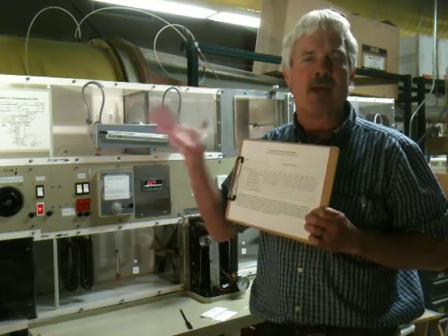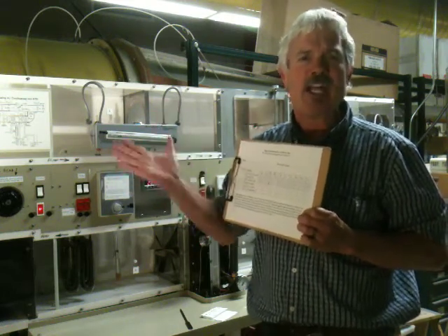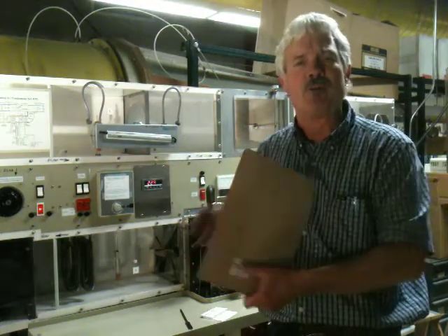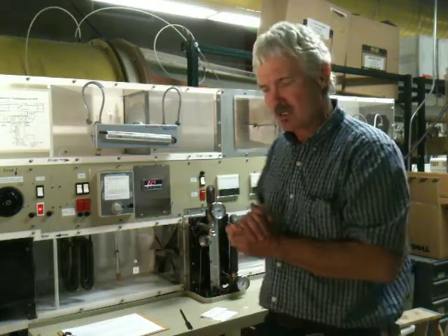And again, the dry bulb is a measure of the relative dryness of the air. Sorry, the wet bulb temperature, the difference between the wet bulb and the dry bulb is a measure of how humid the air is or is not. The greater the difference, the more dry the air is. So if you inject steam, you would expect the wet bulb to increase, which it did, okay?